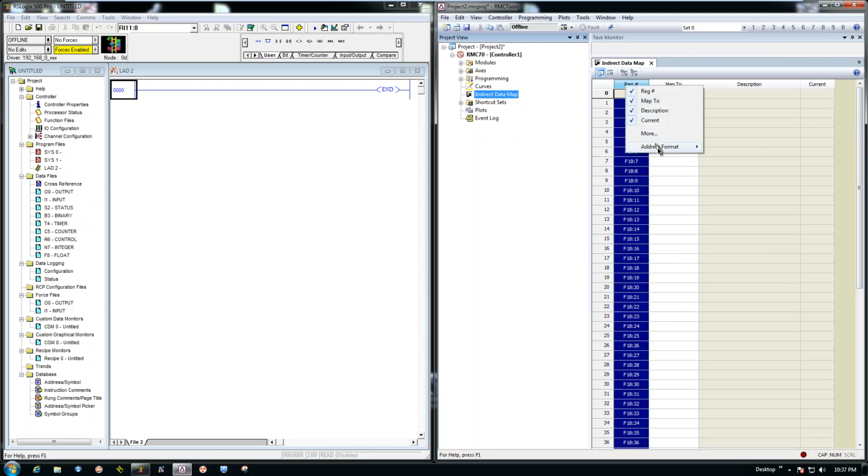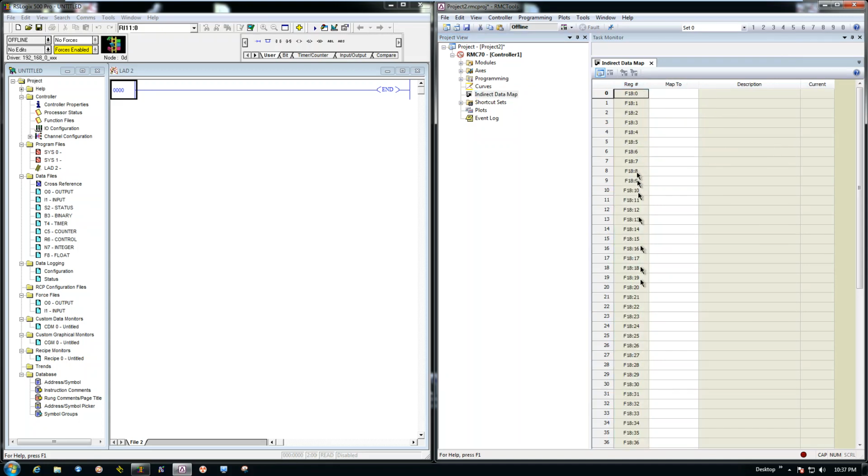Usually, when you first start this up, if you just downloaded it, the RMC Tools software is free at deltamotion.com. It's a free download, but if you start it up, it usually comes out of the box in IEC format, so you're going to see a %MD18. If you want to look at that in the Micrologix format, just go over here to DF1, and it'll give you an F18 number, which is pretty nice because it makes it a lot easier to follow what's going on here. Once we have that done, let's head over to the Micrologix and we'll set that side up first.